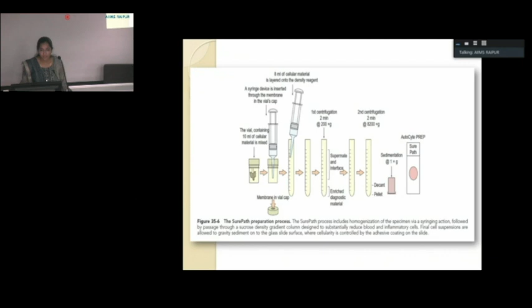Staining with the PrepStain instrument. The slides labeled with the respective numbers of the vial are arranged on the staining rack of the PrepStain machine, and priming of the machine is done before giving the command for staining. First, 1000 microliters of buffer deionized water is added to the cell pellet. Then the instrument picks up a disposable tip and mixes the resulting solution by flushing in and out of the disposable pipette tip 8 times.